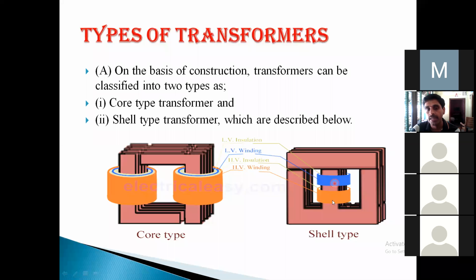You can see blue and yellow color. This orange color is high voltage winding. This blue color is low voltage winding. If you see here, blue colored one near to the core, and orange color one is away from the core, because the low voltage winding can be easily insulated. That's why that is kept near to the core.